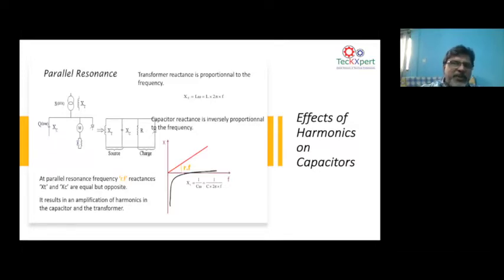That is why whenever you put simple capacitors in your power network, you have to be extremely careful, because these capacitors, instead of improving power factor, can increase your harmonics. So that is a slide showing this. And this increase in harmonics happens due to parallel resonance. Now the next slide.